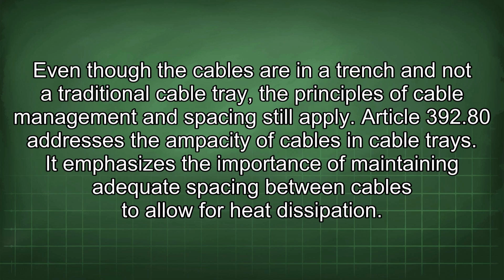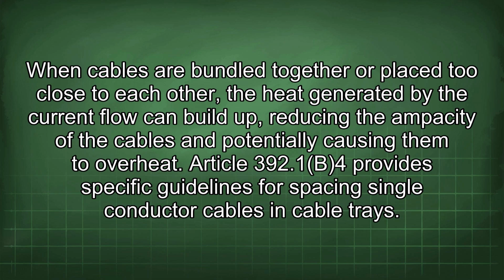Article 392.80 addresses the ampacity of cables in cable trays. It emphasizes the importance of maintaining adequate spacing between cables to allow for heat dissipation. When cables are bundled together or placed too close to each other, the heat generated by the current flow can build up, reducing the ampacity of the cables and potentially causing them to overheat.